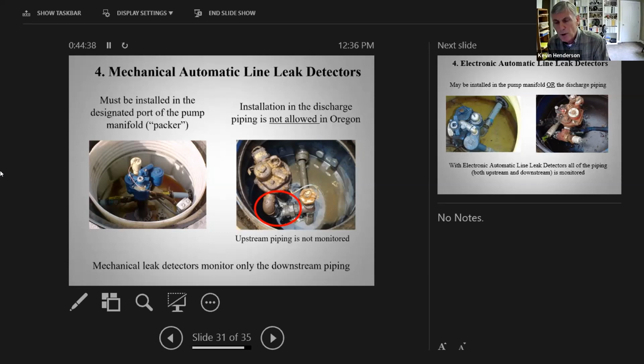And so the piping that is to the left, or upstream part, of that T is not monitored by the mechanical leak detector. So if you had a leak in that union or one of those nipples or that 90 there, the leak detector is not capable of detecting that. And so for that reason, you cannot have a leak detector installed outside of the submersible pump like this. Most states will allow you to put that special T immediately in the discharge of an STP, but you cannot have that 90 and those nipples and that union between the STP and the leak detector. They simply cannot see any pipe upstream of the leak detector.